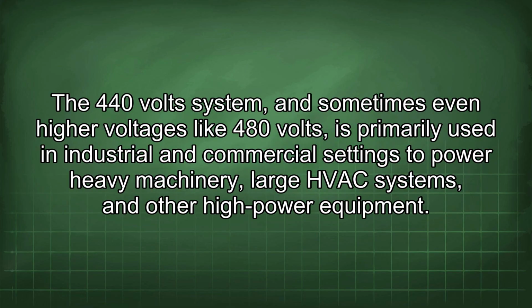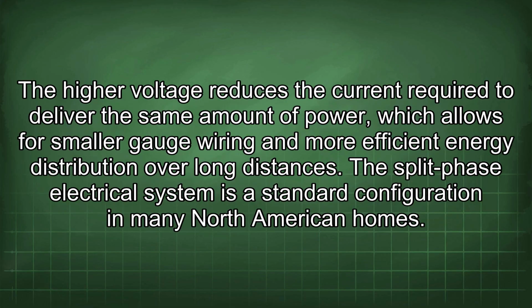The 440-volt system, and sometimes even higher voltages like 480 volts, is primarily used in industrial and commercial settings to power heavy machinery, large HVAC systems, and other high-power equipment. The higher voltage reduces the current required to deliver the same amount of power, which allows for smaller gauge wiring and more efficient energy distribution over long distances.